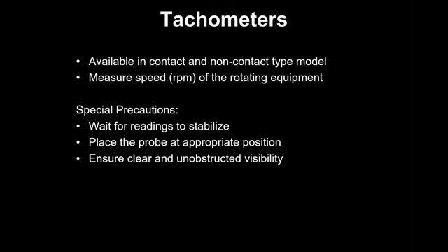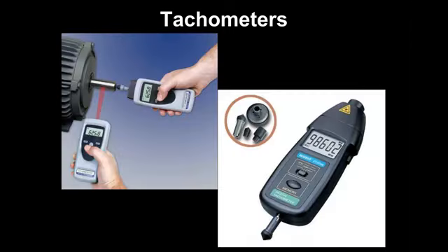You measure the motor RPM, you measure the equipment RPM, and take the pulley ratio. Based on that, you can find out theoretically what should be the RPM and actually what is the RPM. For that, tachometers are available. Now again, tachometers are outdated, we don't use them. But just for you to understand this, there are two types, non-contact type and contact type. Contact type you have to connect directly. Non-contact, you have to put some tape on the rotating surface. That becomes impossible because for that you need a stoppage. So that's how we stopped using it.